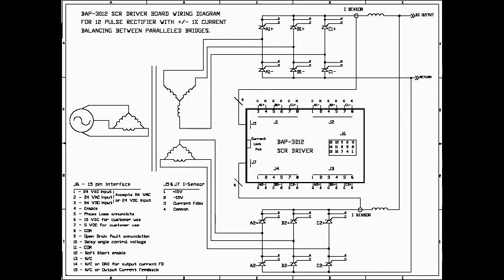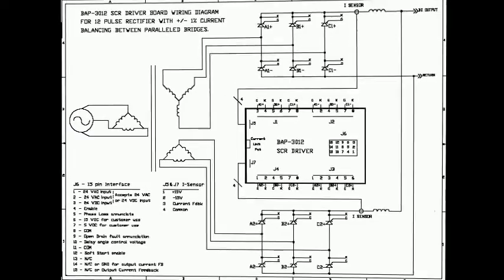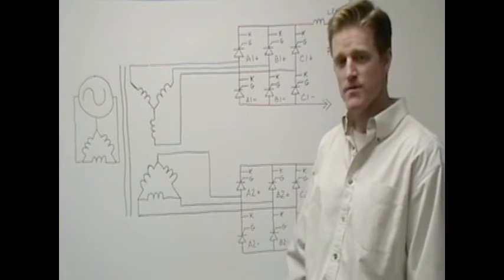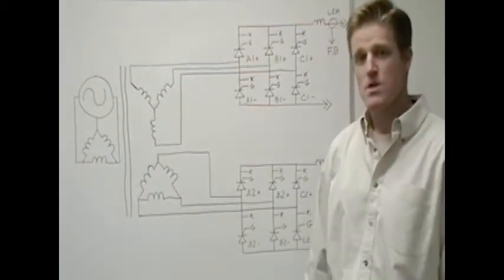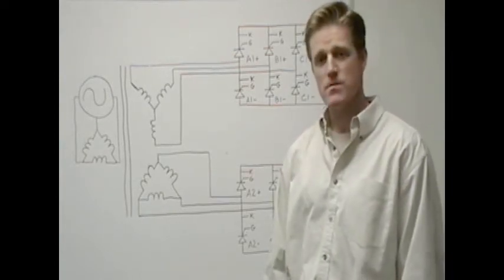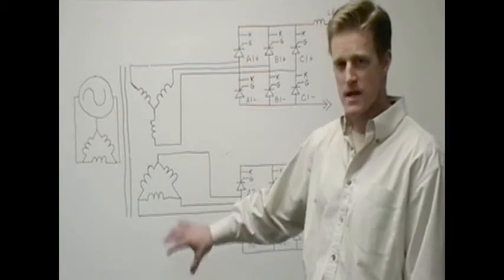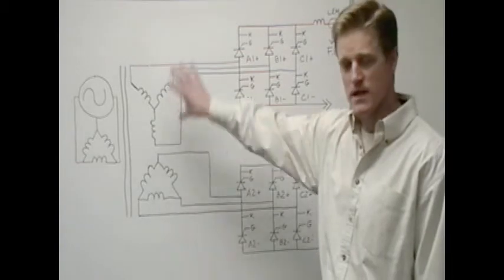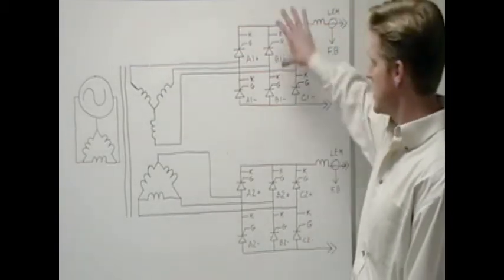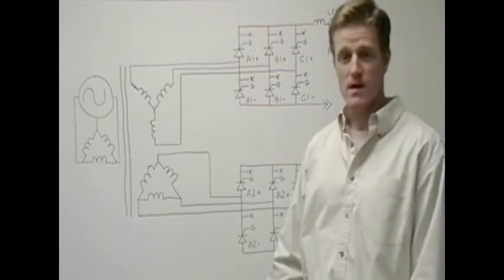Regardless of what topology you select, you will often have undesirable mismatches in the currents out of the parallel bridges. This is due to the mismatches in the turns ratios of the transformer secondaries. In order to create a 12 pulse rectifier, you need a 30 degree phase shift between the two secondaries. Transformer manufacturers do the best they can to match the turns ratios out of these secondaries, but it often results in a finite mismatch in the voltage out of these secondaries, which creates a mismatch in the voltages of your bridges.